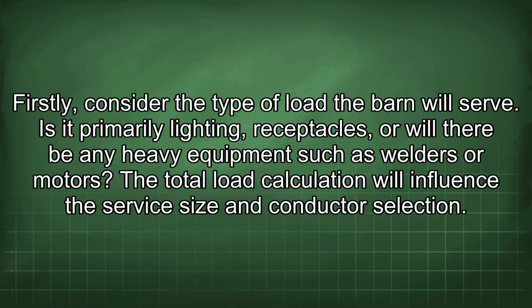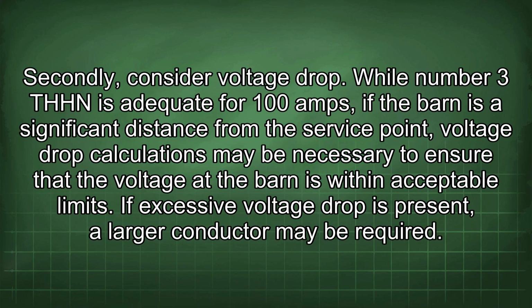Firstly, consider the type of load the barn will serve. Is it primarily lighting, receptacles, or will there be any heavy equipment such as welders or motors? The total load calculation will influence the service size and conductor selection. Secondly, consider voltage drop. While number 3 THHN is adequate for 100 amps, if the barn is a significant distance from the service point, voltage drop calculations may be necessary to ensure that the voltage at the barn is within acceptable limits. If excessive voltage drop is present, a larger conductor may be required.